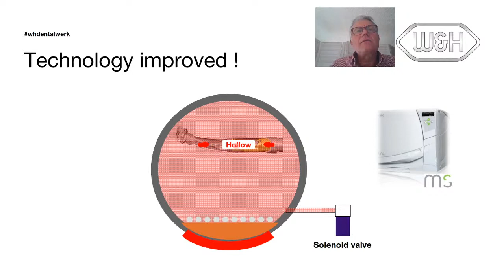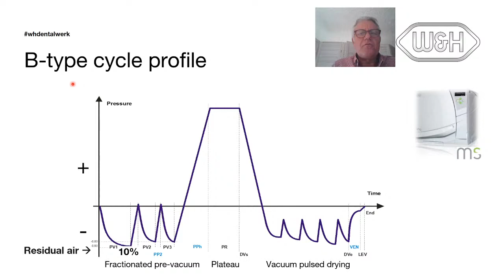This is called B, it comes from big sterilizer. It's actually medical grade sterilization, and it does a very nice pre-vac by running a first vacuum phase. You see the video here. First vacuum phase that removes 90% of air. Second vacuum. So we reach, after 3 vacuum and pressure pulses, because this machine mounts a vacuum pump, you have almost 0% air and 99.9 steam. So it guarantees steam penetration in pouched, even double pouched instruments. It guarantees the processing of the most challenging devices, instruments you can use in dental practice.